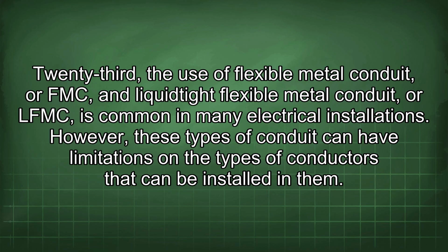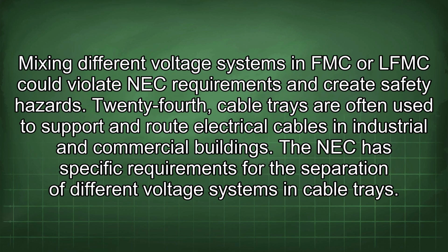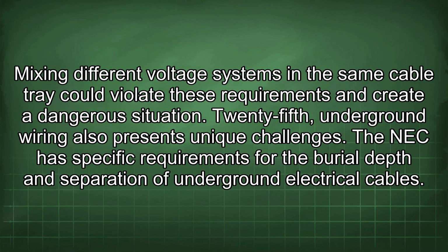23rd, the use of flexible metal conduit, or FMC, and liquid-tight flexible metal conduit, or LFMC, is common in many electrical installations. However, these types of conduit can have limitations on the types of conductors that can be installed in them. Mixing different voltage systems in FMC or LFMC could violate NEC requirements and create safety hazards. 24th, cable trays are often used to support and route electrical cables in industrial and commercial buildings. The NEC has specific requirements for the separation of different voltage systems in cable trays. Mixing different voltage systems in the same cable tray could violate these requirements and create a dangerous situation.